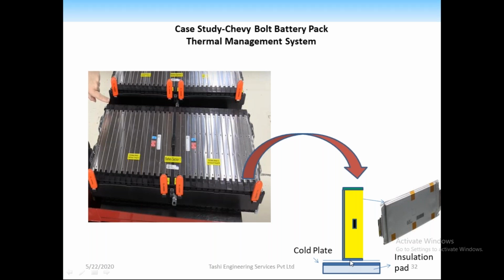The heat flow direction — the black color signifies the tape. The heat generated in the yellow portion is transferred to the aluminum fin, then to the cold plate, and out of the battery pack. The important thing here is the thermal pad. If we don't use a thermal pad, we can't ensure that all of the aluminum fin is in contact with the cold plate.